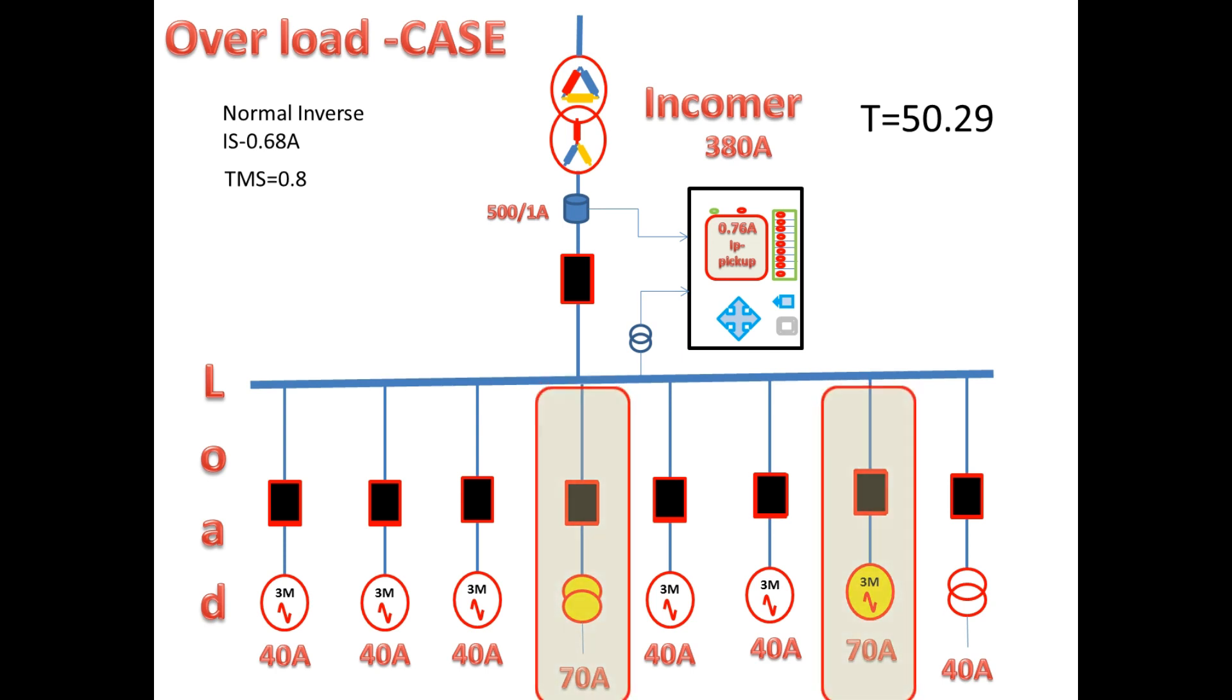In this case, if the feeders get normal or if these two feeders get tripped by their own CB before 50.29 seconds, then the incomer still continues to serve and remaining healthy feeders will get supply. Because since it has high tripping time, this transformer and motor can become normal or its breaker can be tripped due to thermal protection.